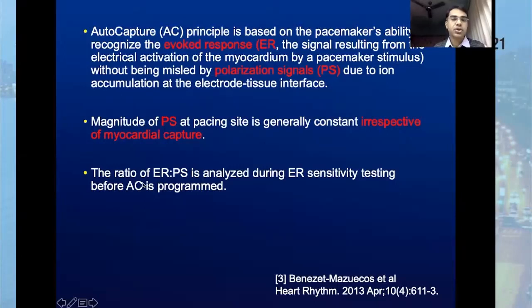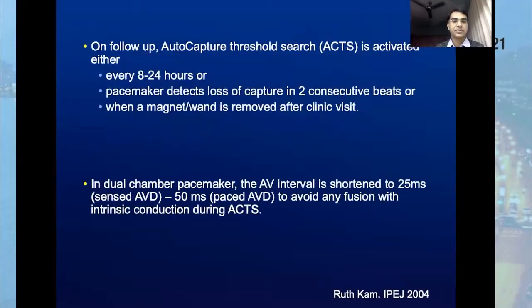So whenever the auto capture feature is switched on in the beginning, it always assesses an evoked response to polarization signal ratio. And when this ratio is favorable, the device recommends programming auto capture, and only then should we program the auto capture function.